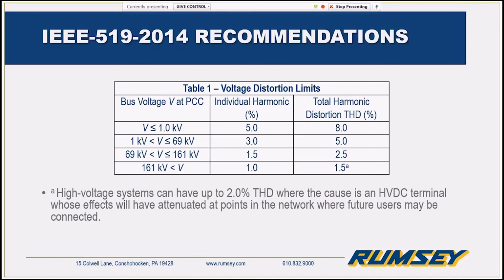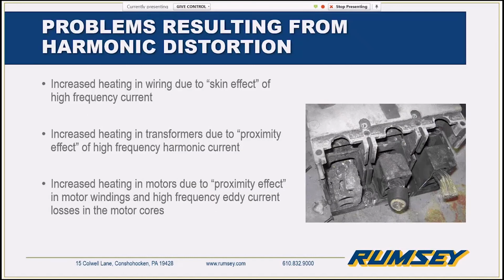They also raised the voltage distortion limits for many customers from 5 to 8%. Most of the time when you're looking at the applications that we work with, we're falling in with the 5 to 8% requirement there. Some of the other problems that we see when we're looking at harmonic distortion. So most of the time you're going to be looking at an active filter, again, is with IEEE 519. But as more and more facilities are increasing their total number of nonlinear loads, we see more and more problems occurring. So one of the more common ones is equipment overheating.